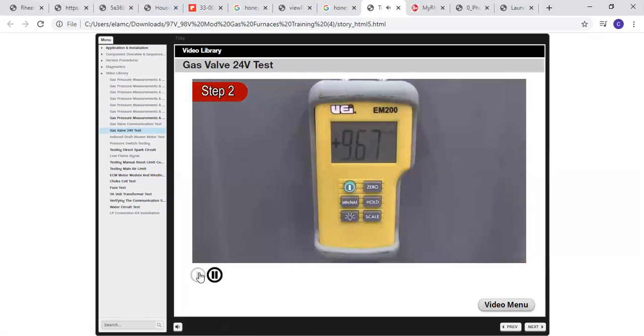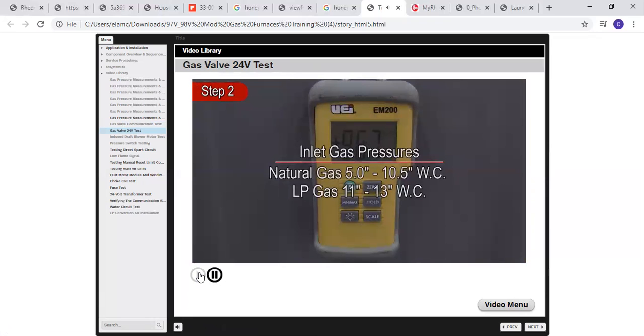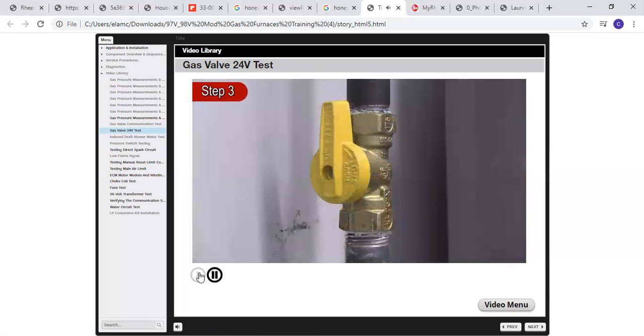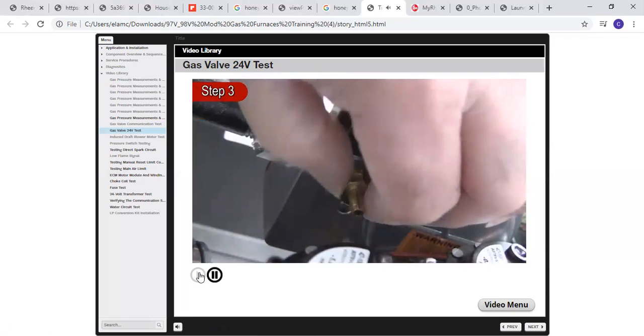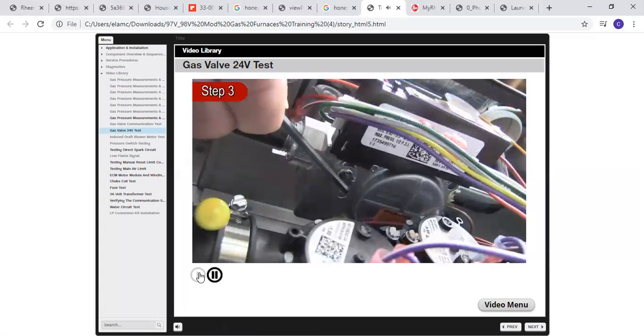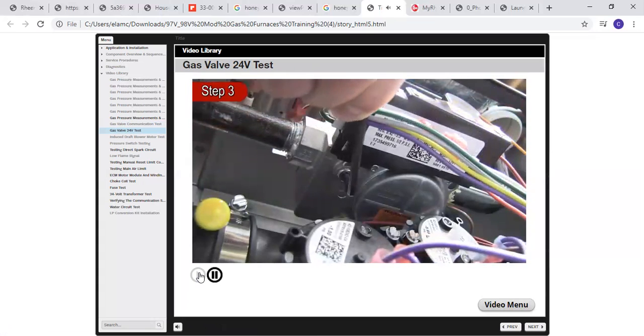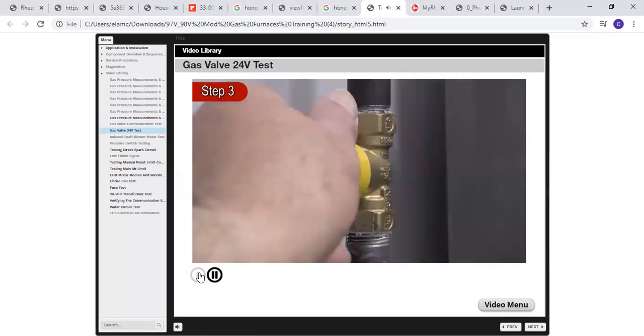Measure the inlet gas pressure. Confirm the gas supply to the furnace is above the minimum required inlet pressure. Step 3. Shut off the gas supply and remove the gas manometer from the inlet pressure port and replace the inlet pressure port plug on the gas valve. Turn on the gas supply to the furnace.